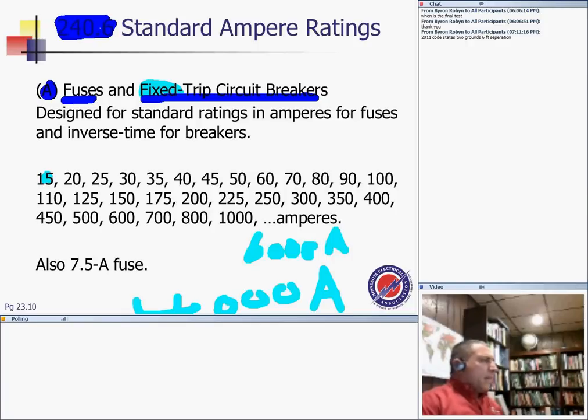Anybody have seen anything higher than 4,000 amps? 4,000 amps switchgear. Not a lot of people do, actually 3,000 amps. So these are standard circuit breakers. Which means if you end up with non-standard, you can custom design yourself a fuse or a circuit breaker and pay an arm and a leg, or go to the next standard up, or the next standard down, depending on the circumstances.